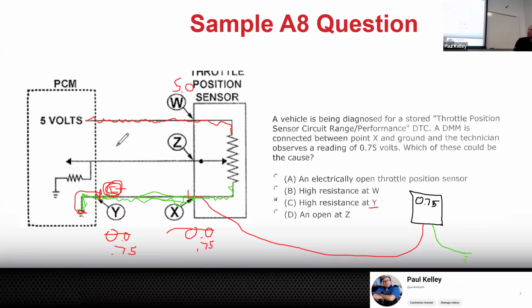This wire right here has a range of about, you're going to get used to this number, 0.5 to 4.5. And the reason why is this is going to sweep. If you're way up here, that's going to give you like a 4.5, because look, it comes out as 5 volts, it goes through just a little bit of resistor. This drops 4.5 over the whole length. If you're in the middle, it'll be at like a 2.5. But if this is swept up to the top, you only drop a little bit, you'd probably get the 4.5 number. But if this were to be down here, you'd probably get like the 0.5 number.